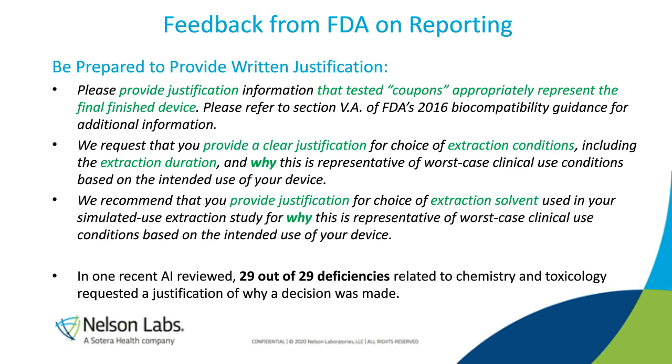So let's pause there and think about that for a second. For a long time, and by we, I mean the chemistry and toxicology community at large, it's been pretty common to use extraction conditions from ISO 10993-12 and also repeated in 10993-18, 50 degrees C for 72 hours. And this has been more or less standard, or the FDA has asked for exhaustive extraction conditions, where you extract for a duration of time until you're down to 10% or less per unit time of total extractable amounts.